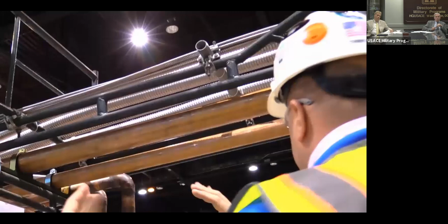One thing to notice back there: these are all our zone valves for the medical gas. These zone valves are going to run directly straight down for all the tents, and that's where we're going to control all the medical gas. The tanks are just going to roll like this. So these are all your zone valves that will control all the medical gas that feeds all the way down to the front of the space. That's how we're able to isolate each pod if we did have a problem.